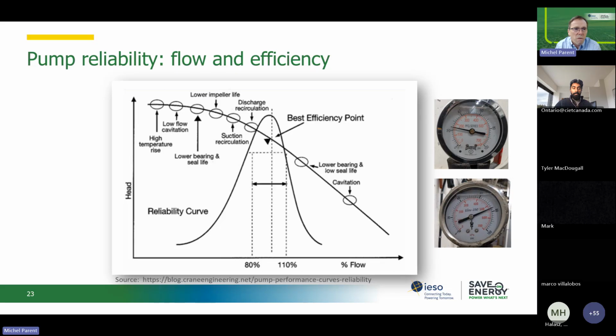So how do we resolve that? There are two ways to resolve that oversizing of a pump. You either throttle the pump, which was the old-fashioned way. You get the balancer to come in. The balancer takes the delta P across the pump, says that delta P is too low, I need to throttle the pump to go to the delta P that the design engineer told me to get. So that's why you see the two gauges I put on this slide. You need to check what the delta P is across your pumps.